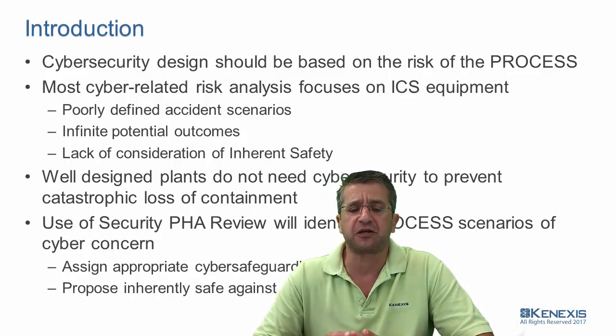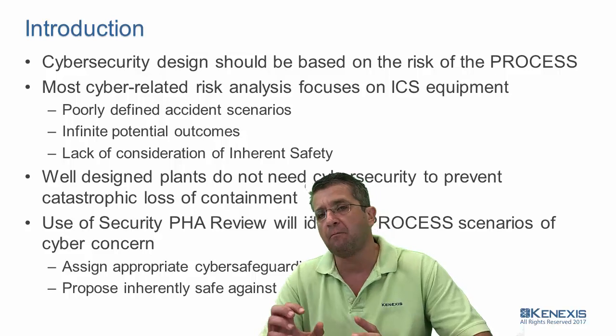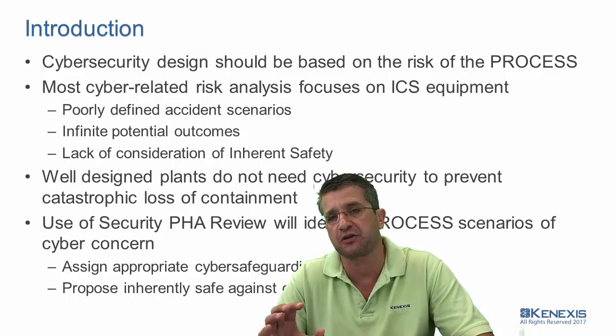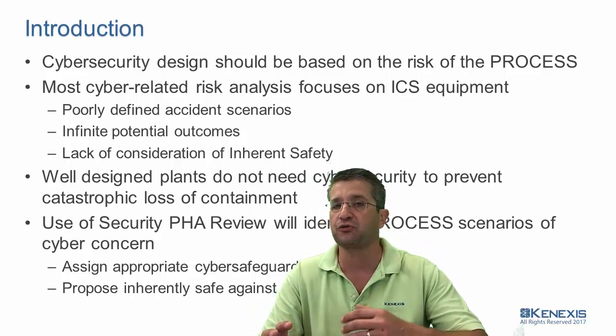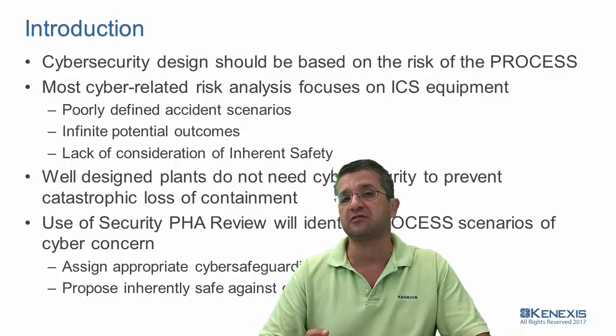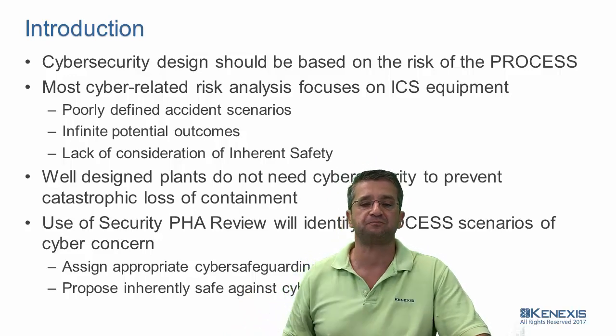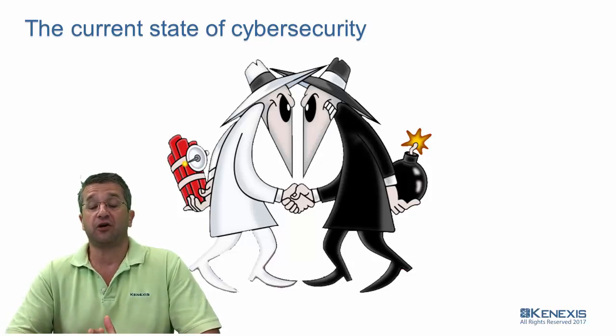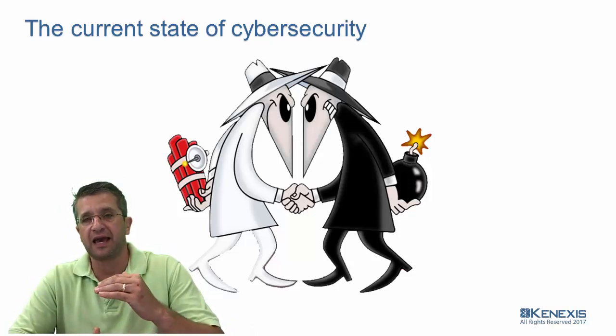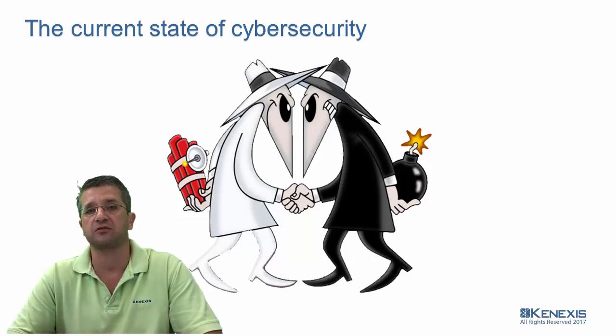When we use a SPR — a Security PHA Review — that's going to help us identify what process scenarios a cyber attack might be able to take advantage of to cause a loss of containment. When we identify those scenarios, we want to make sure we've either assigned the appropriate amount of cyber safeguarding through an IEC 62443 security level, or we can make the plant inherently safe against cyber attack by proposing mechanical safeguards. The HSE groups, the safety groups, and the process groups need to be involved to make sure cyber attacks can't cause loss of containment events.